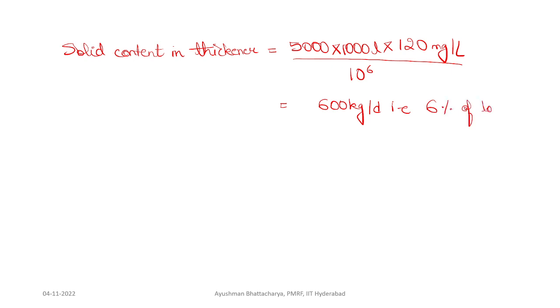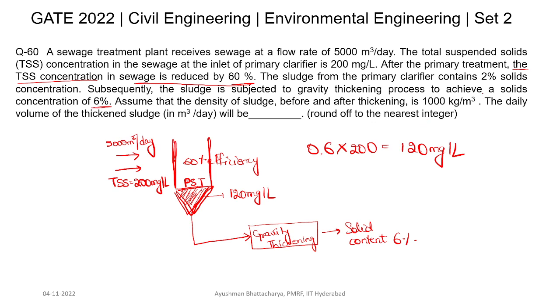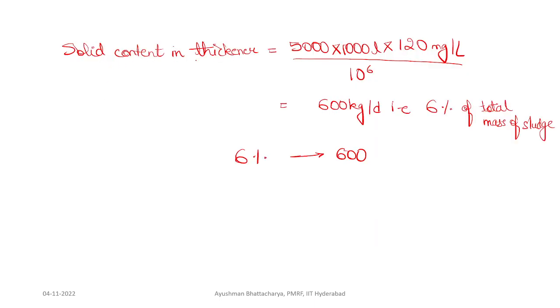That 600 kg per day is 6% of the total mass of sludge — because the question states the gravity thickening achieves a solid concentration of 6%. So if 6% of the total sludge mass is 600 kg, then total mass of sludge = 600 ÷ 6 × 100 = 10,000 kg per day.